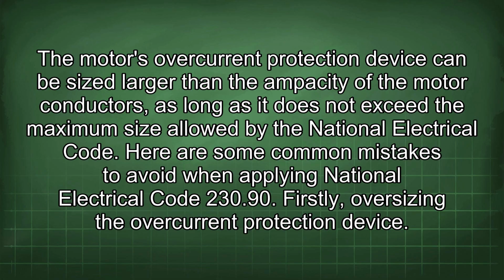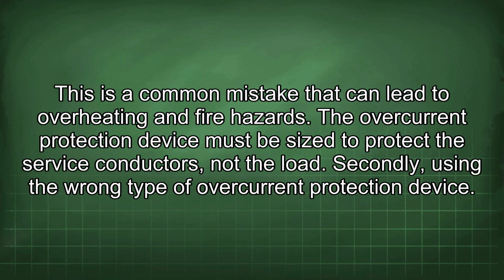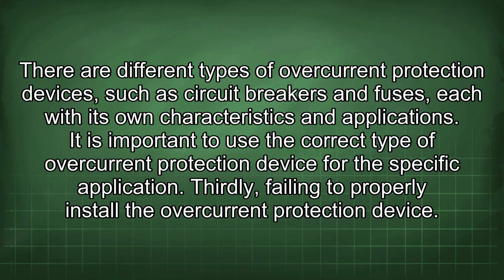Here are some common mistakes to avoid when applying National Electrical Code 230.90. Firstly, oversizing the overcurrent protection device. This is a common mistake that can lead to overheating and fire hazards. The overcurrent protection device must be sized to protect the service conductors, not the load. Secondly, using the wrong type of overcurrent protection device. There are different types of overcurrent protection devices, such as circuit breakers and fuses, each with its own characteristics and applications. It is important to use the correct type of overcurrent protection device for the specific application.